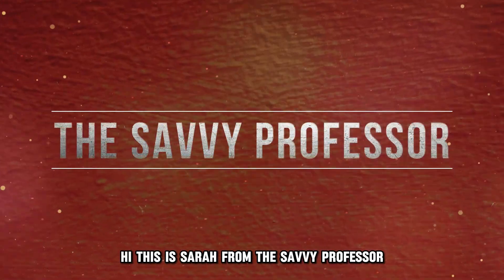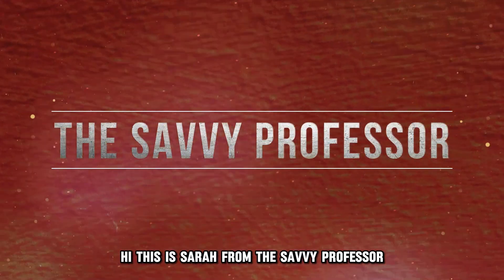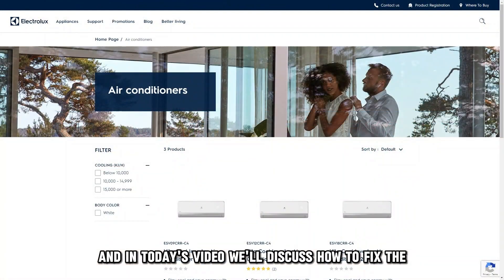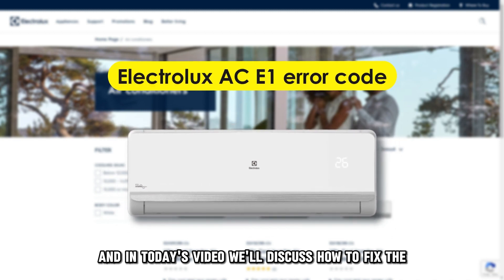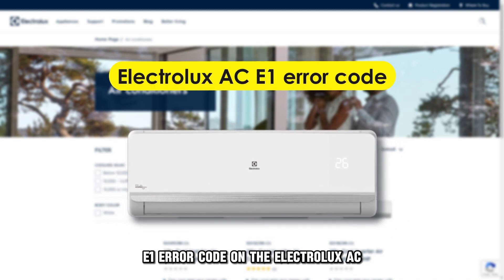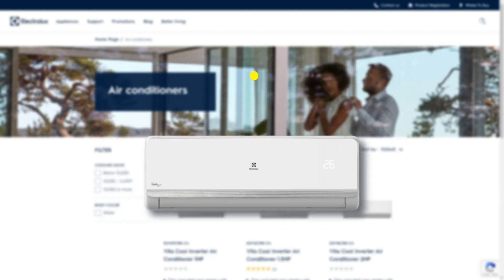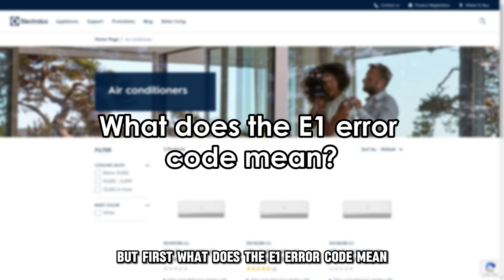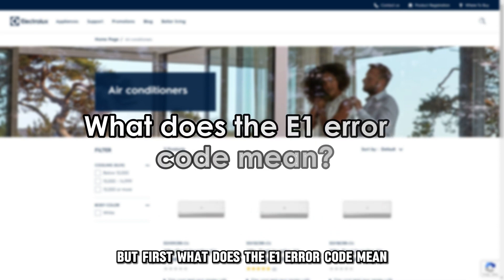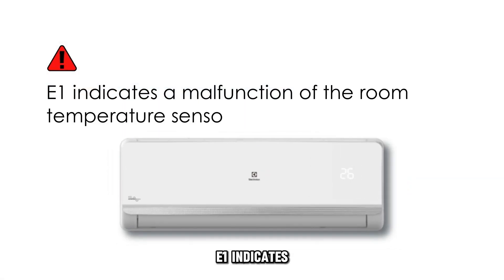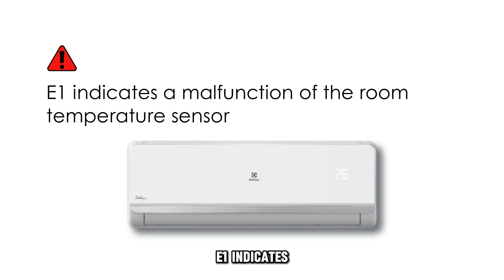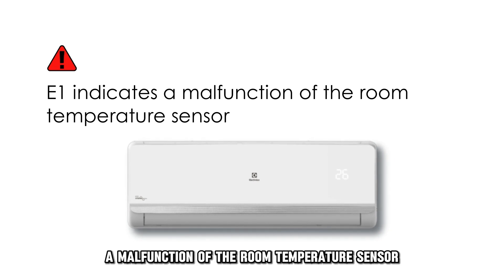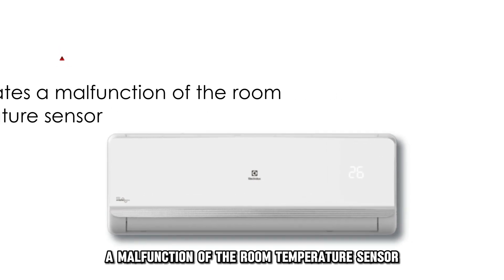Hi, this is Sarah from The Savvy Professor, and in today's video we'll discuss how to fix the E1 error code on the Electrolux AC. But first, what does the E1 error code mean? E1 indicates a malfunction of the room temperature sensor.